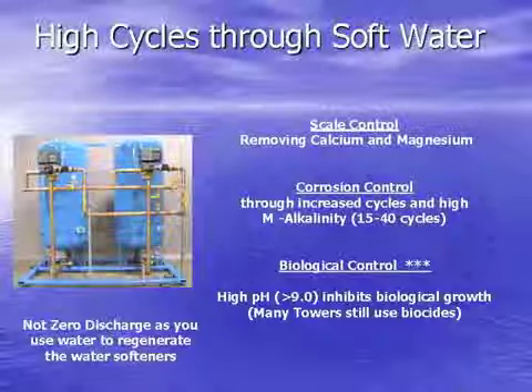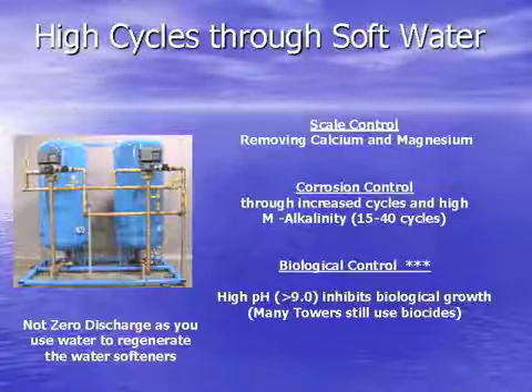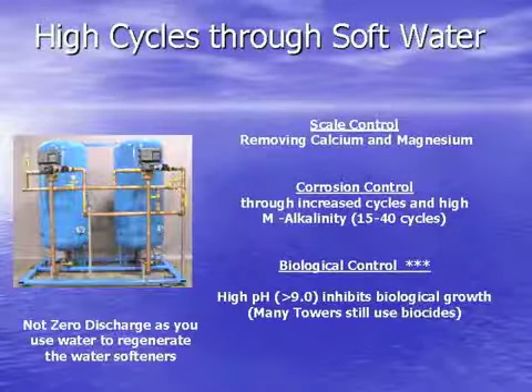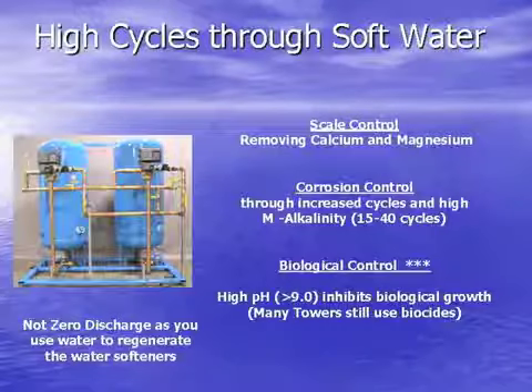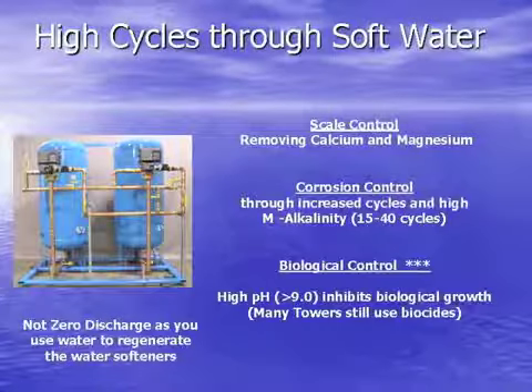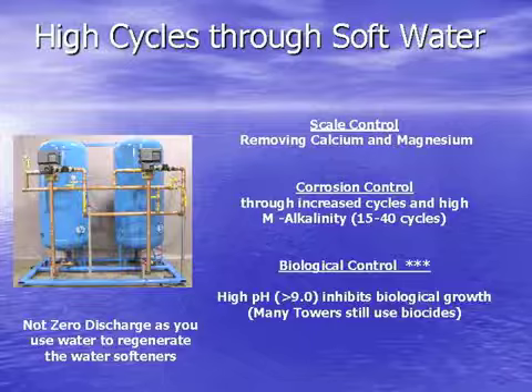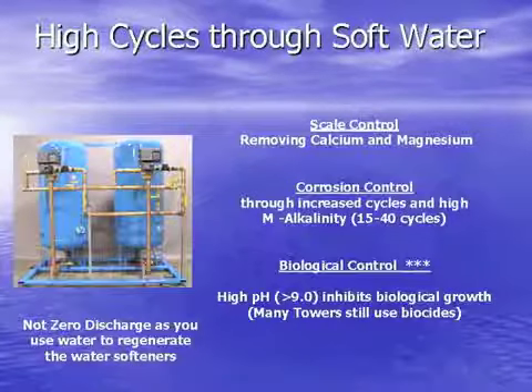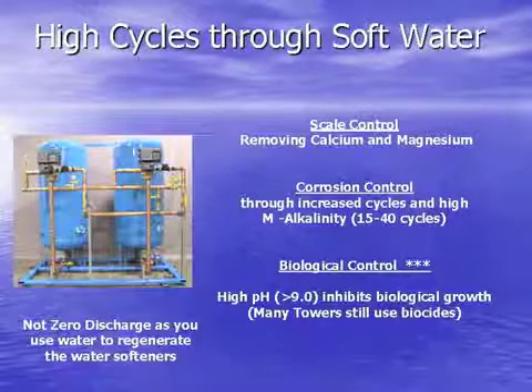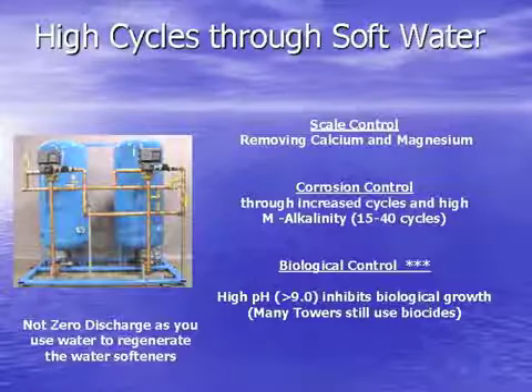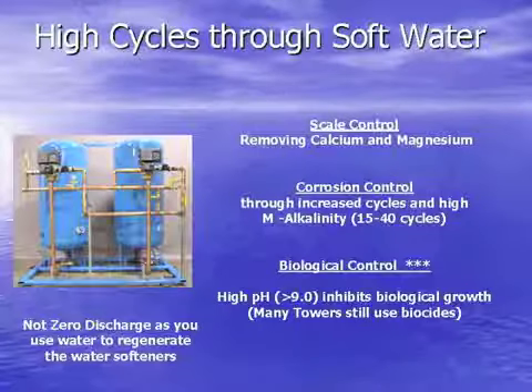If you're looking at some of the systems, especially we see in California, we also see this in high hardness areas around the country. They actually put softeners on the system, and the purpose is to remove the calcium out of the water, which is fine. That's how you control scale. So we understand the scale control mechanism through using water softeners is to remove the calcium and magnesium out of the water. The corrosion control is fairly simple.